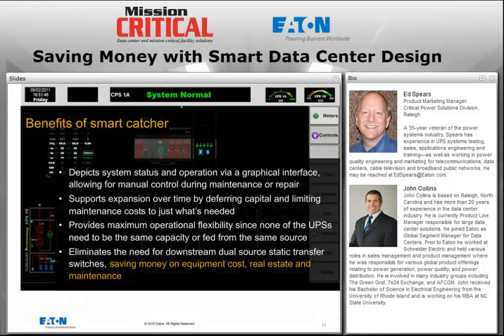If we look at the next slide here, we see a little bit more elaborate system. It's been covered up a little bit by the text, but this shows both the primary UPS and, in this case, about five primary UPSs and one catcher. But the idea here is to describe the benefits of the smart catcher. It depicts the system status operation via a graphical interface. It's easy to see what the power flow is and who's online and who's on bypass and who's being supported by the catcher or not. It's a quick one-screen drawing, without having to follow a lot of lines to be able to tell what the status of the system is and what the capacity is going forward.